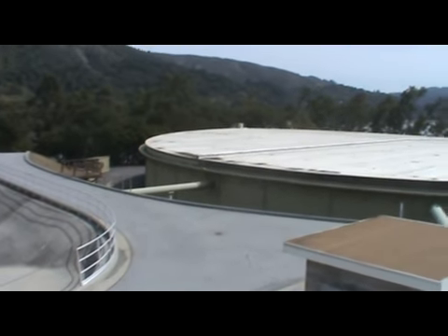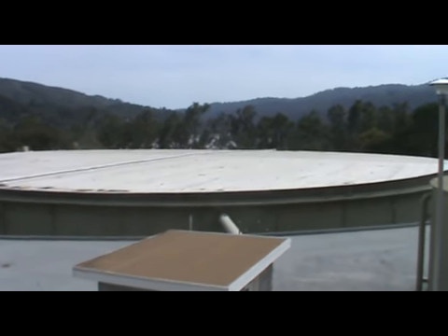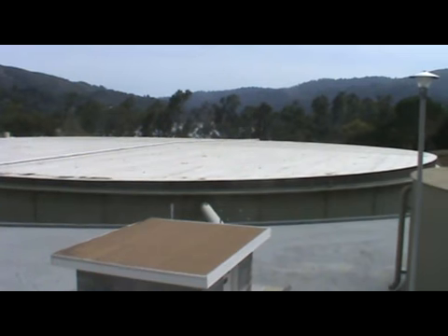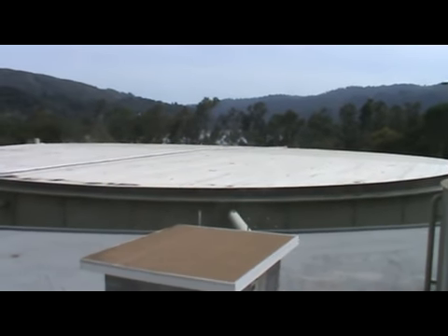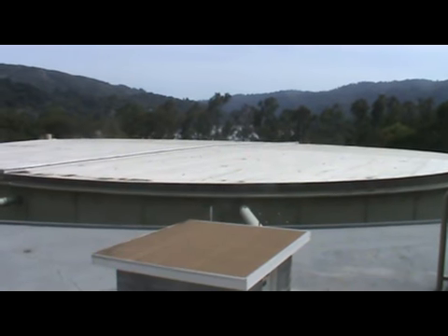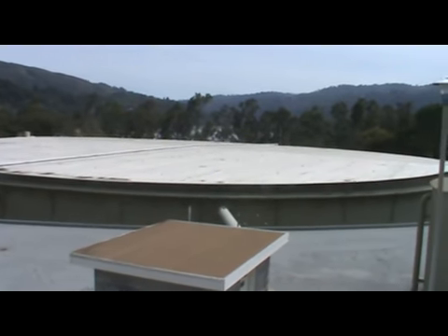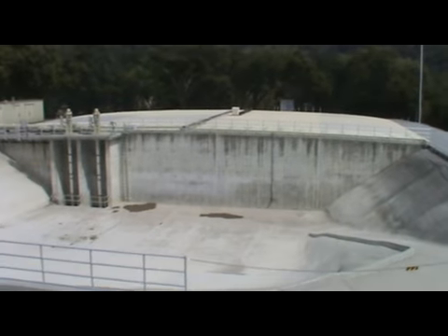And then the water is sent to a holding tank, which is called a clear well. In this case, that is the clear well. What the clear well does is allow for contact time before going out into the system, so that anything that might still be in the water has time for that chlorine to react with it and kill it. This plant has 2 clear wells. There's that one right there, and there's another one on the other side of that wall.